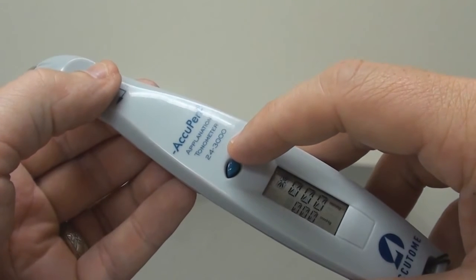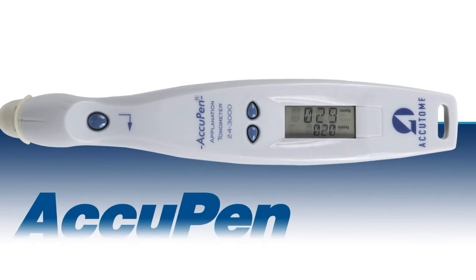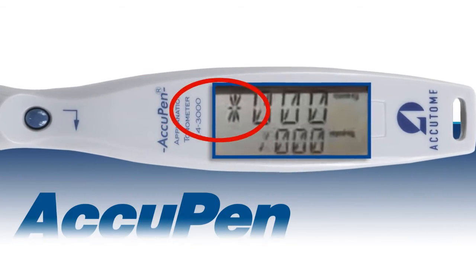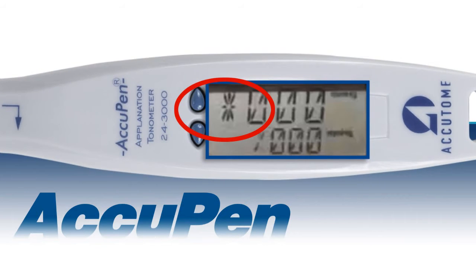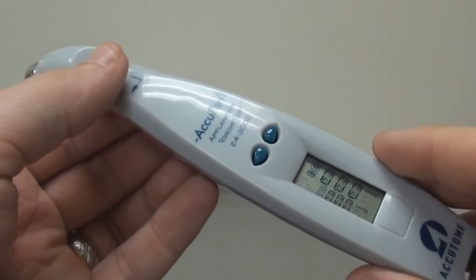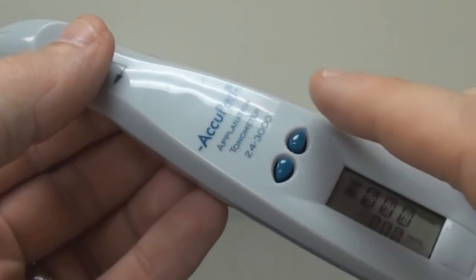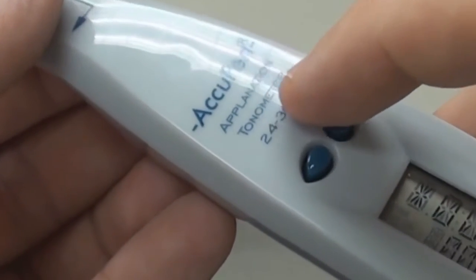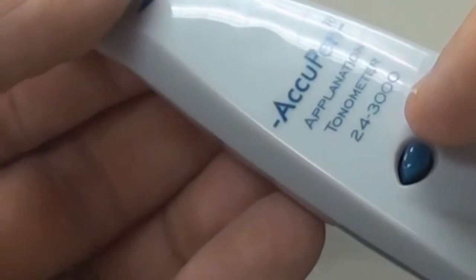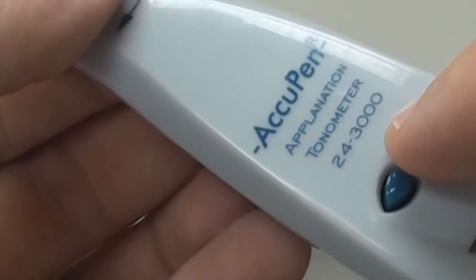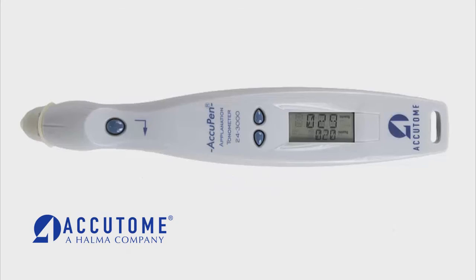When multiple measurements have been captured, an asterisk next to one of the numbers will indicate the furthest from the average. To delete individual measurements, hold down one of the arrow buttons for approximately 3 seconds. The unit will chirp indicating the measurement on the screen has been deleted. After deleting one measurement, the accupen will automatically update the average IOP measurement.